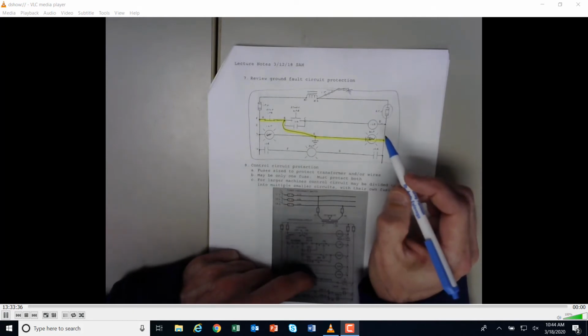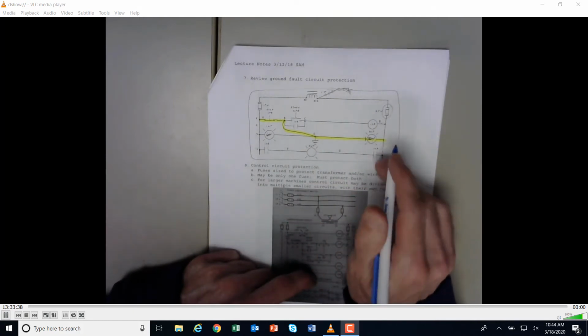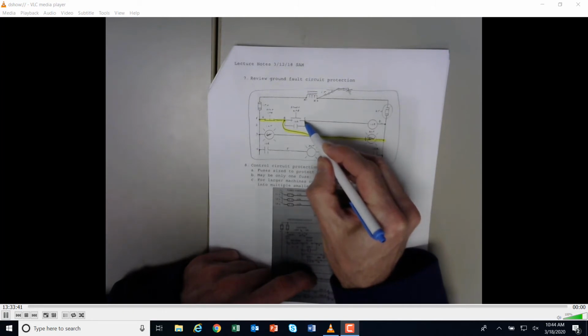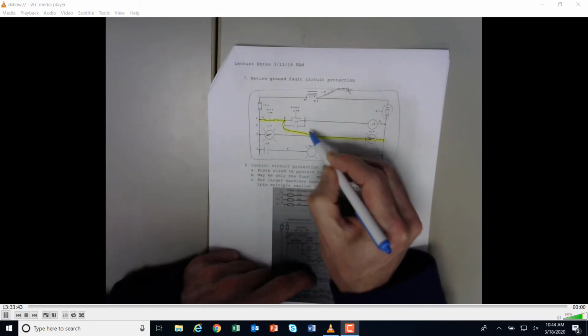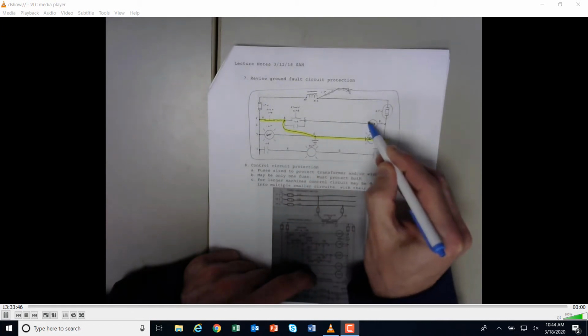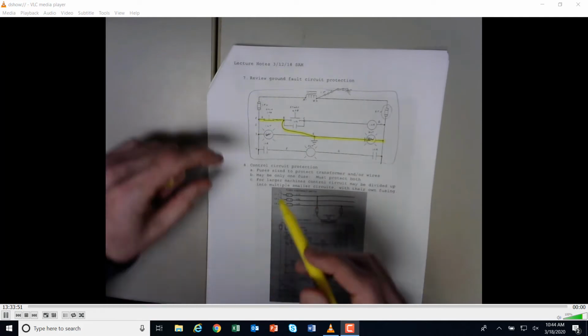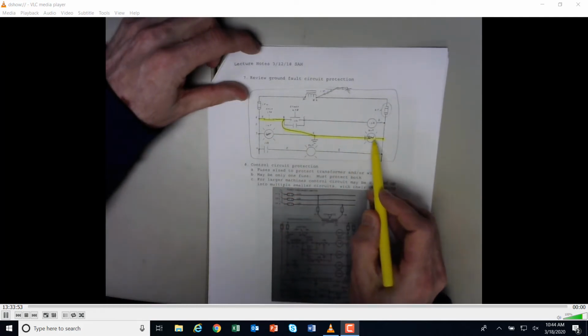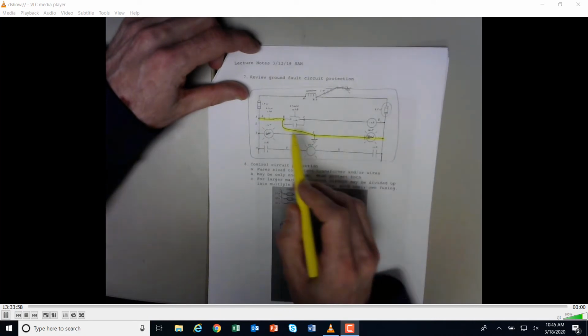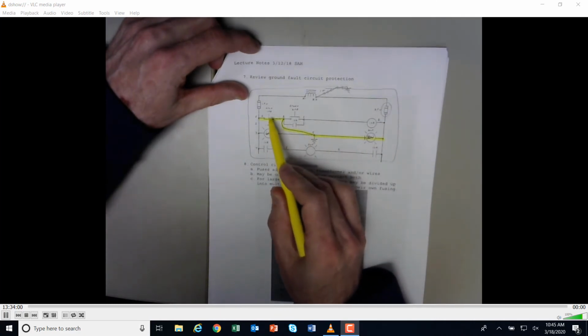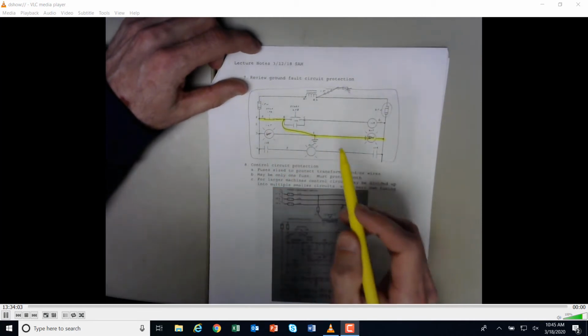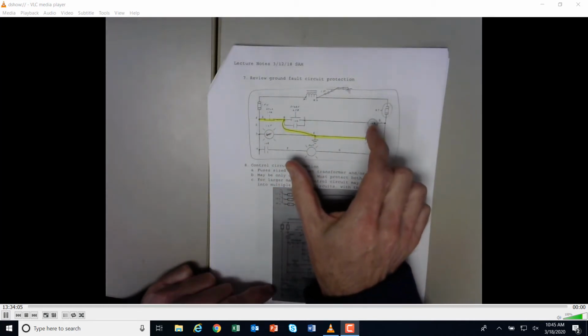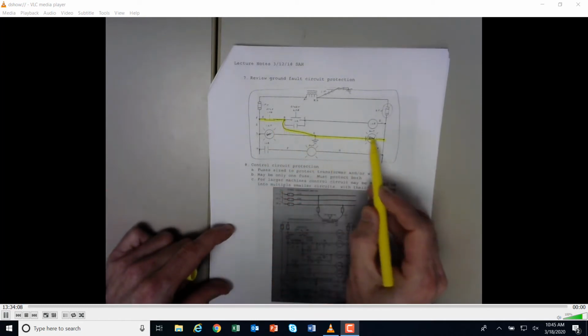Now, as you start working your way through here, you'll see that sometimes we'll create the ground fault from C or from A, and the electricity will pass different ways. As you draw it with the marker here, you want to follow it and create the path of the least resistance for this flow, and it'll say whether you push the stop button or start button or whether the relay's on or everything like that. So that's a brief description of the lab, and you're going to use a highlighter to indicate how this is going, okay?